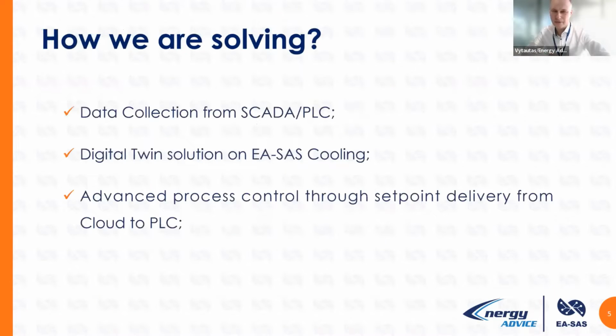And how are we solving this problem? First, of course, we collect data from your SCADA and from your PLCs. If you have SCADA, usually in the SCADA you will have an OPC server, and if you have PLCs, we make direct data collection from the PLCs, adding to your premises only one thing. It is data collection software, which connects to the PLC or OPC, collects data in real time and sends it to the cloud. The digital twin is inside the cloud, which we will discuss later. And we have advanced process control. I mean, from the cloud we send optimization commands back to the PLCs, to your cooling or refrigeration system, in order to increase efficiency and reduce electricity consumption.